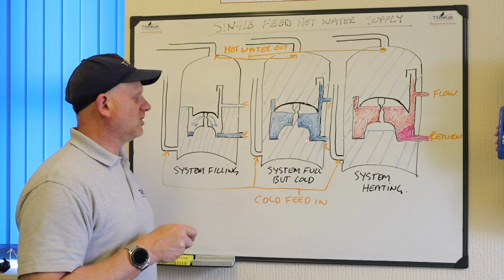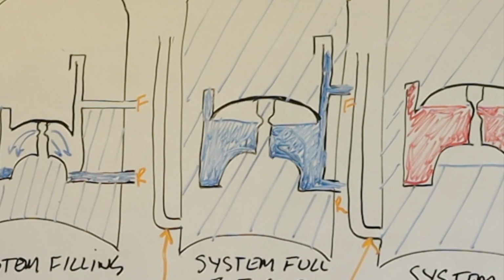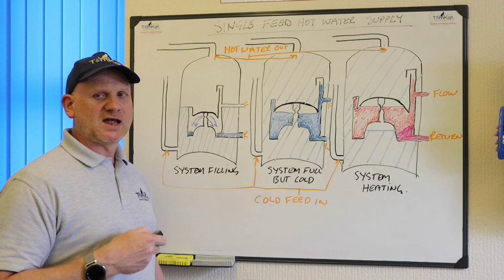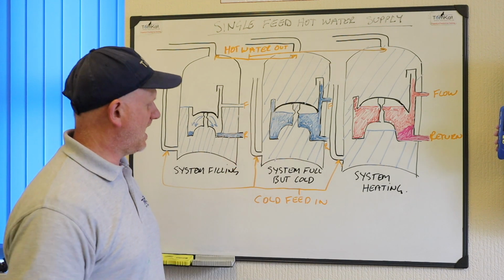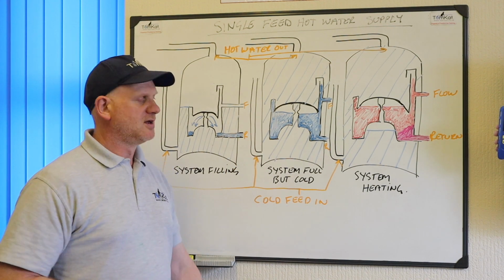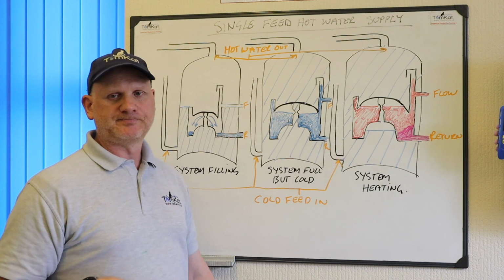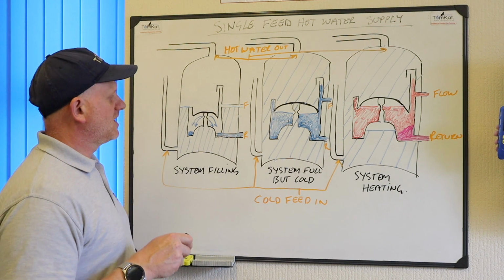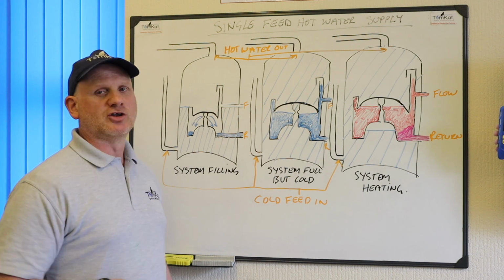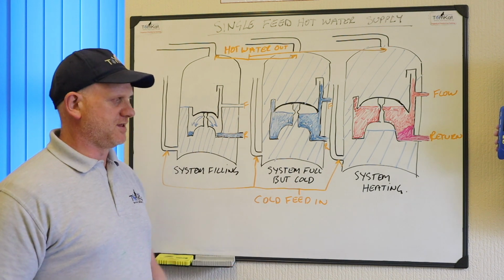Now then, we're fully filling the system up now in the next one. So you can see the actual Primatic and the air bubble is in the top now. And the system is completely full. The cylinder's full with cold water. The central heating's filled through the return and the flow. You've bled all the radiators. Everything's full. Happy days. But the cylinder is cold. Okay? So this water in there is the same water in there. That's why we can't put these chemicals in.